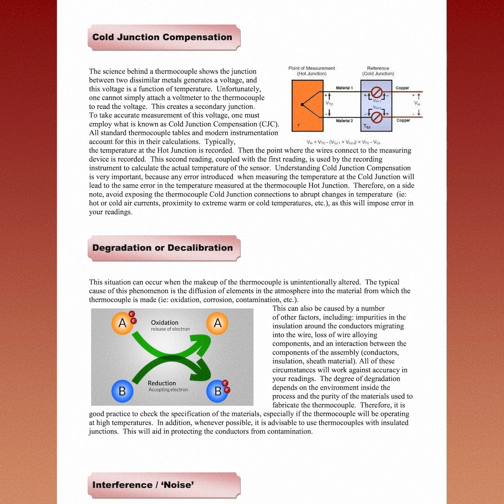Understanding cold junction compensation is very important because any error introduced when measuring the temperature at the cold junction will lead to the same error in the temperature measured at the thermocouple hot junction. Therefore, on a side note, avoid exposing the thermocouple cold junction connections to abrupt changes in temperature, that is, hot or cold air currents, proximity to extreme warm or cold temperatures, etc., as this will impose error in your readings.